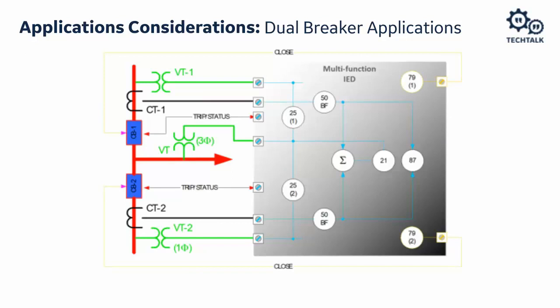The modern digital line differential relay approach has CT1 and CT2 from both breakers connected to relay terminals separately. The 87L function uses per-breaker current to develop proper restraint. Distance and overcurrent functions can still use the summed CTs. Synchrocheck and closure are done per breaker. This is the recommended approach for dual breaker applications.